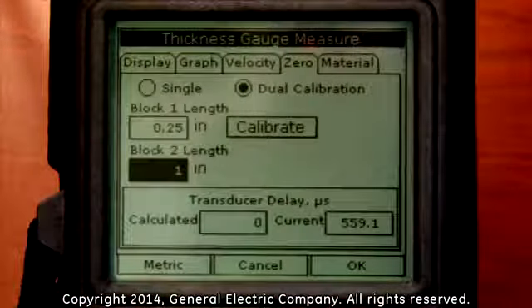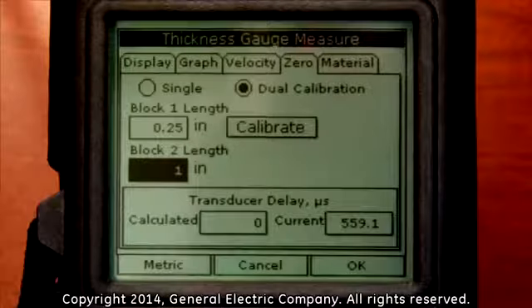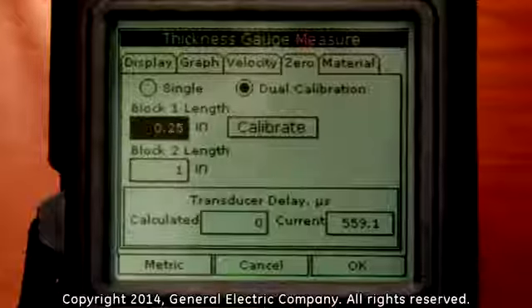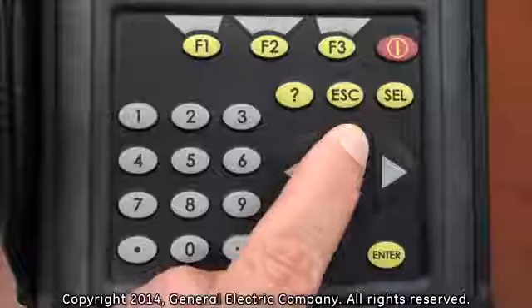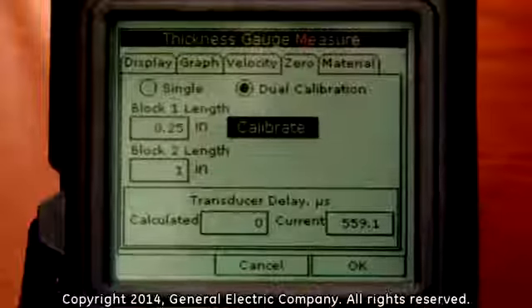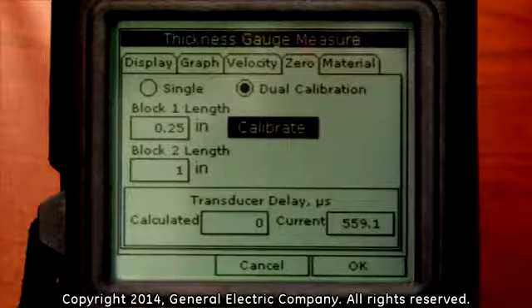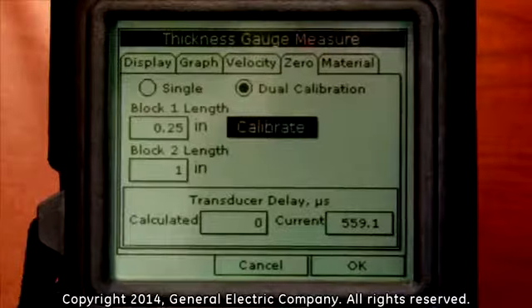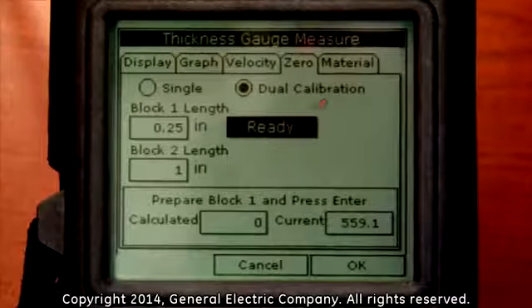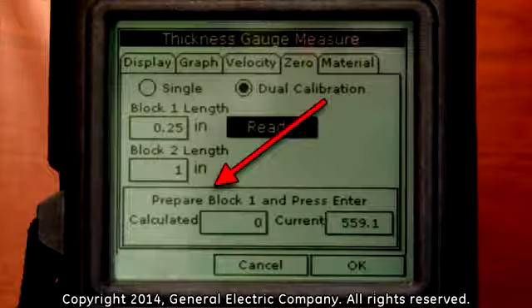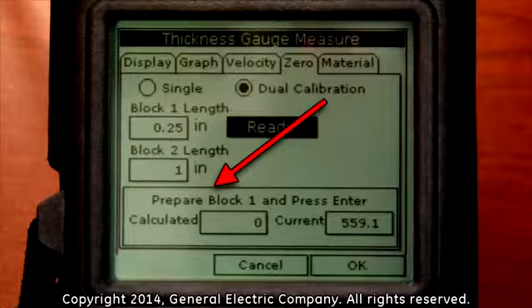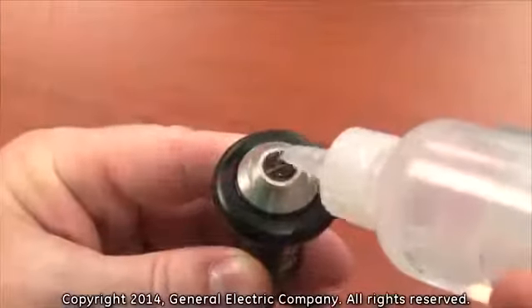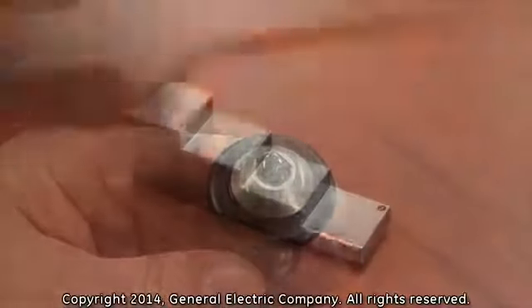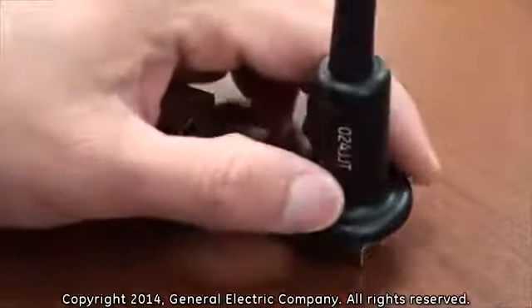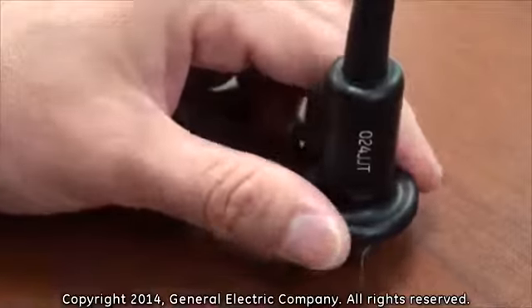Once you have the block 1 length and block 2 length values set, use the up arrow key on the keypad to go back up to the block 1 length, then use the right arrow key on the keypad to highlight the calibration option. With the Calibrate option highlighted, press the Enter key on the keypad. On the bottom of the display screen, you will see a message that tells you to prepare block 1 and press Enter. Apply couplant to the face of the thickness gauge transducer and firmly press the transducer to the 0.25 inch portion of the calibration test block.